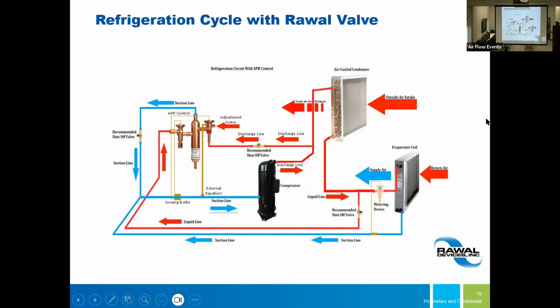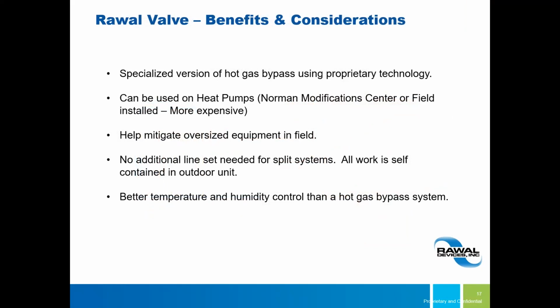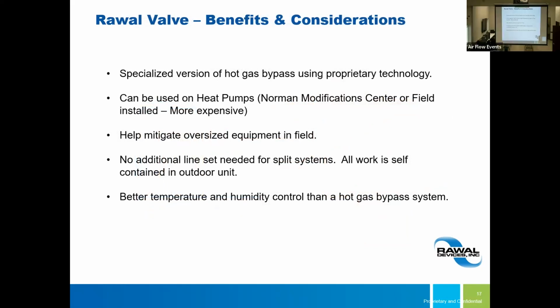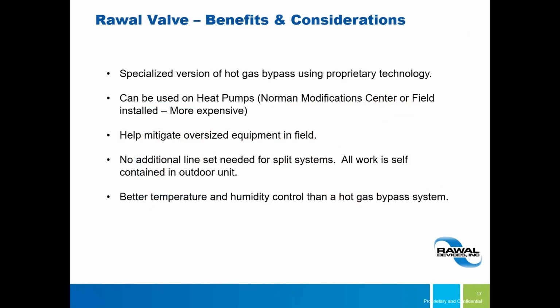And you can retrofit. Yeah. So, that's where I was going to go. When the unit's grossly oversized and they're constantly overcooling, this is the solution. So when you think about the raw valve or Raywall valve, it's a specialized version of hot gas bypass, obviously. So you're using proprietary technology. And you can use this on heat pumps. And one of the things that I noted is that our modification center has the option to factory install Rawal valves on our units. And obviously I don't know what other manufacturers are doing, but this can also be done in the field.